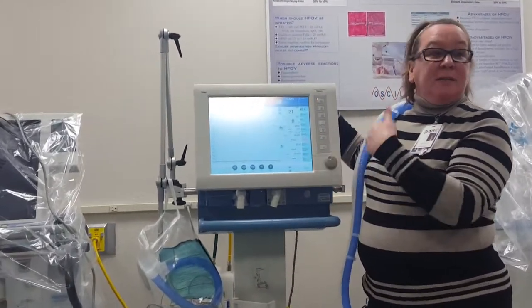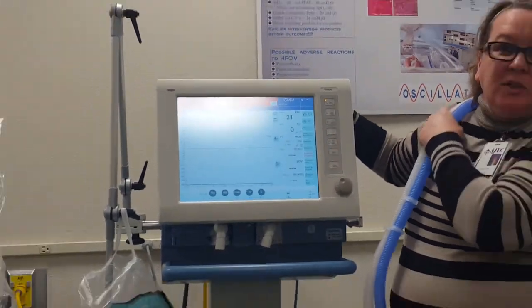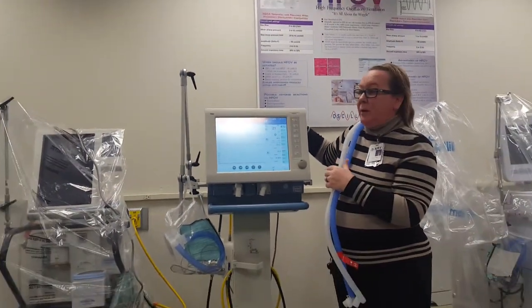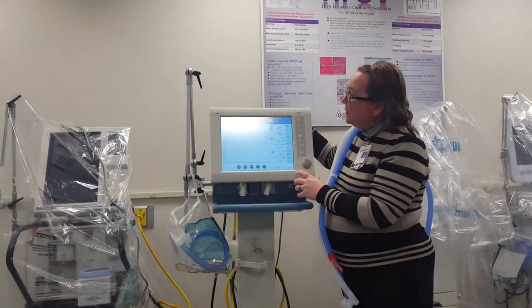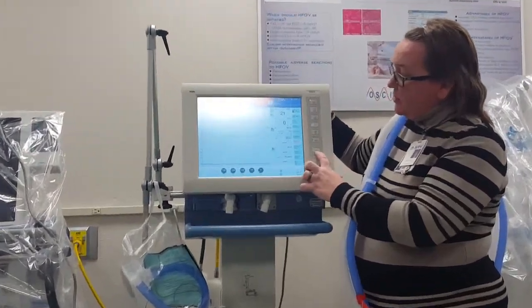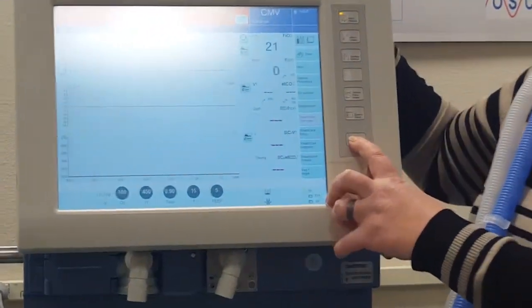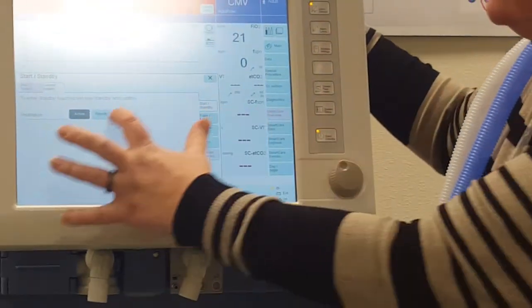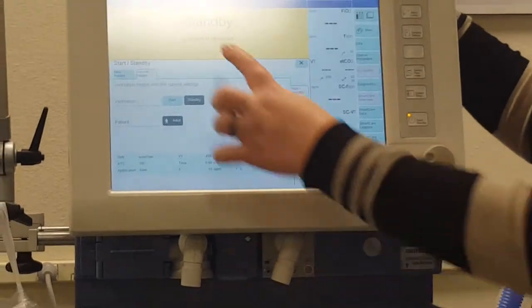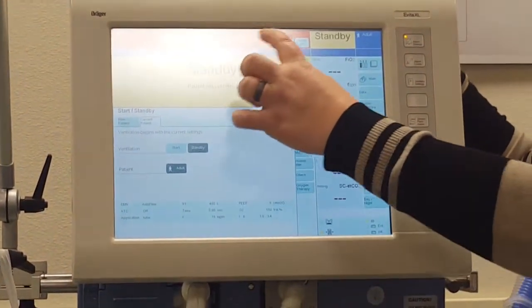So you have to put it into standby. You could never be doing a calibration on a vent while it was on a patient, so they always want to be in standby. To put this into standby, it's a two-part step. Hit the start standby button, and then hit the standby here, put it into yellow, confirm it. And then up here at the top it says standby activated.